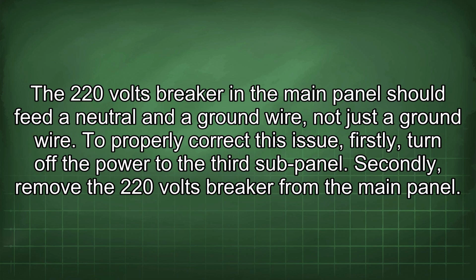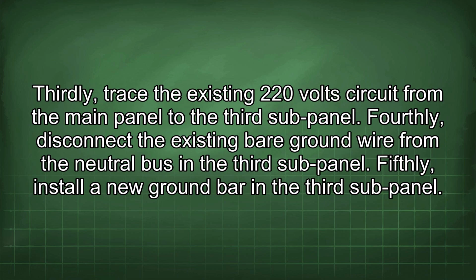wire. To properly correct this issue, firstly, turn off the power to the third subpanel. Secondly, remove the 220 volt breaker from the main panel. Thirdly, trace the existing 220 volt circuit from the main panel to the third subpanel. Fourthly, disconnect the existing bare ground wire from the neutral bus in the third subpanel. Fifthly, install a new ground bar in the third subpanel.